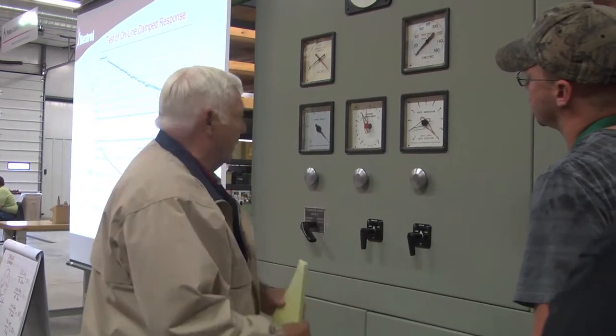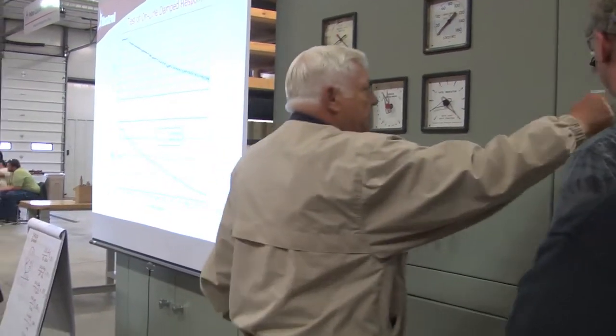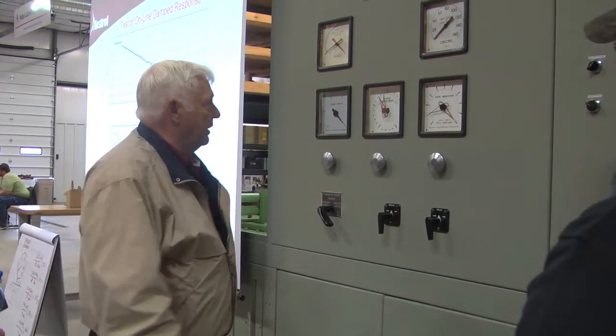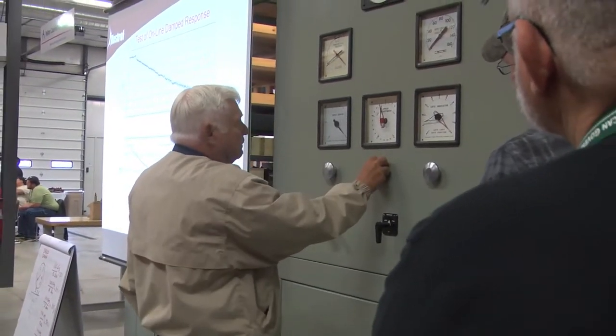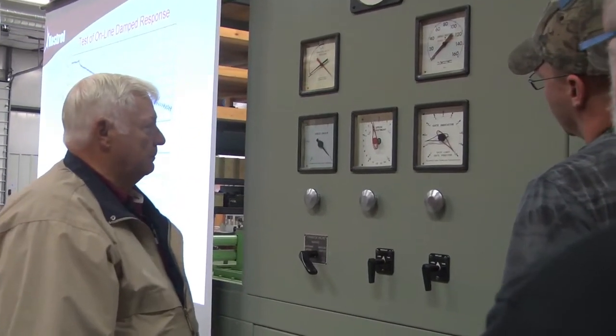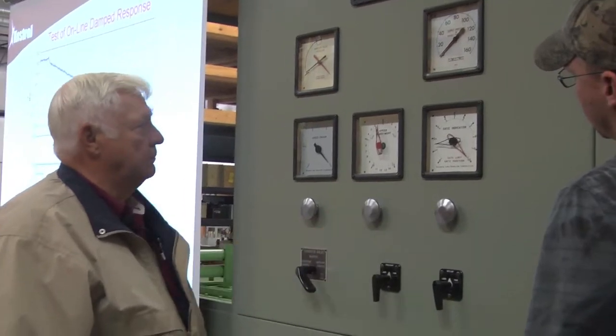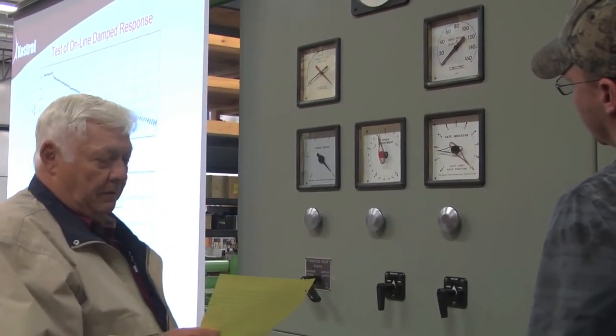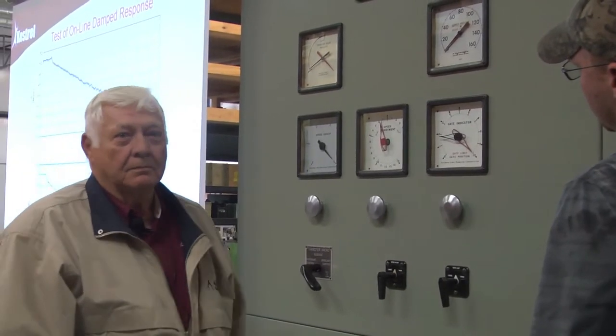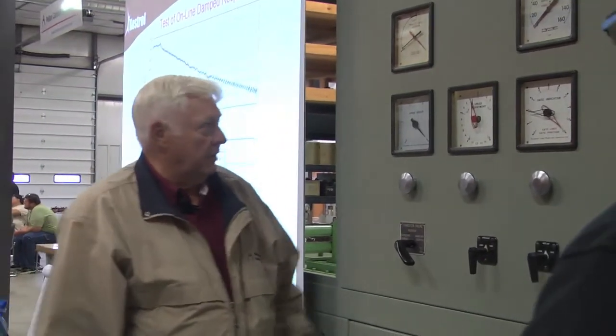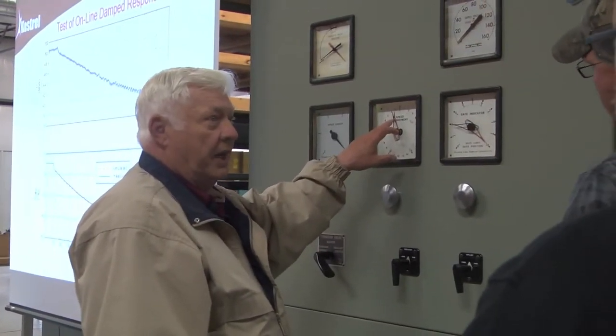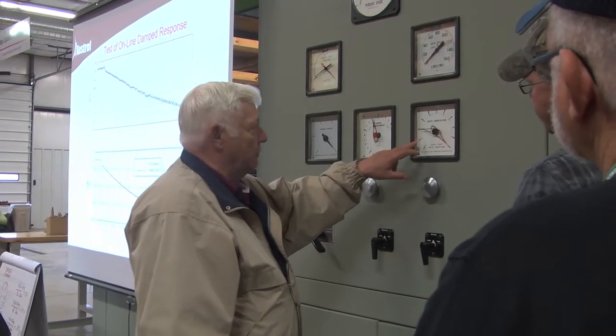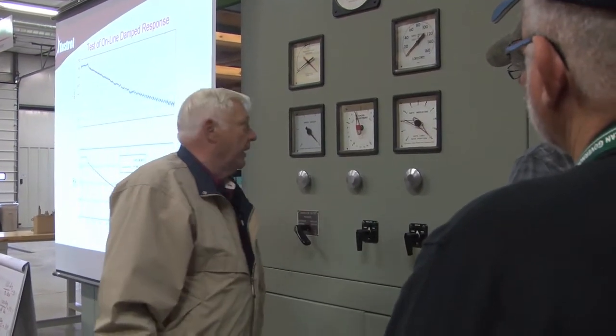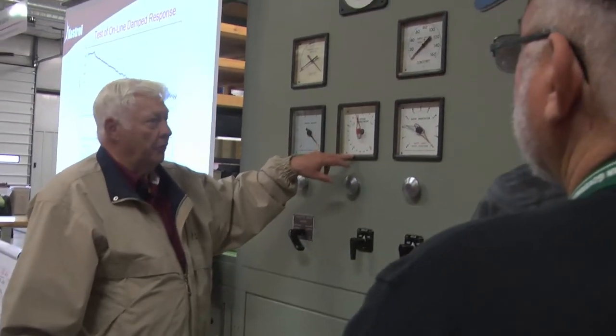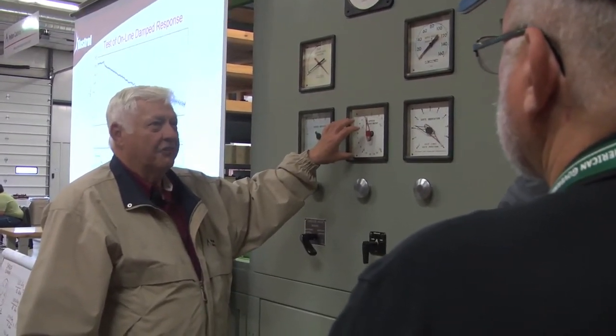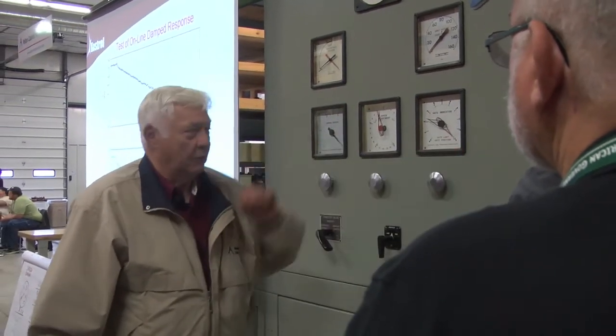So what we're going to do, I have to get to 30% gate, and I want to see how long it's going to take to get there, okay? I'm going to give it one shot. It's going to take approximately 3 to 4 minutes to get all the way there. I gave it a 1% change. The gates have to move 20%, so they've got to move from 10 to 30. Now, it wouldn't make any difference if I change this a half a turn, 1 turn, or 5 turns. It's going to take the same amount of time to get where it's going, okay?